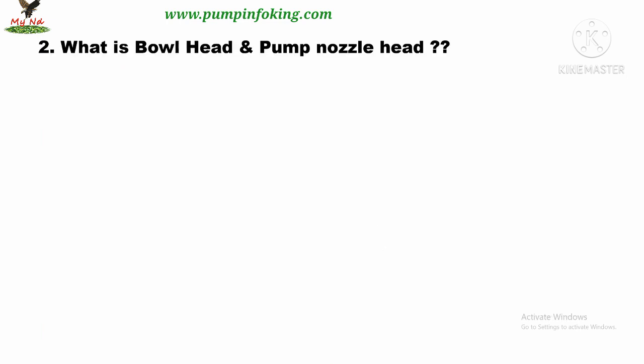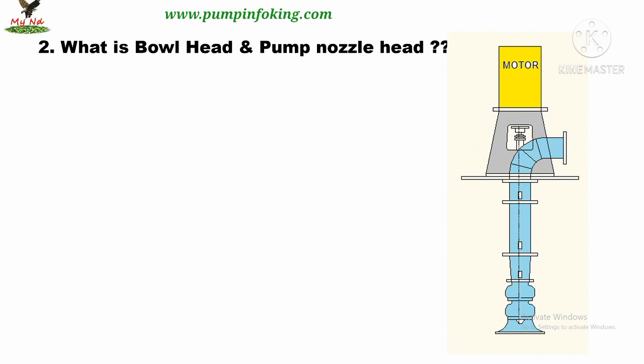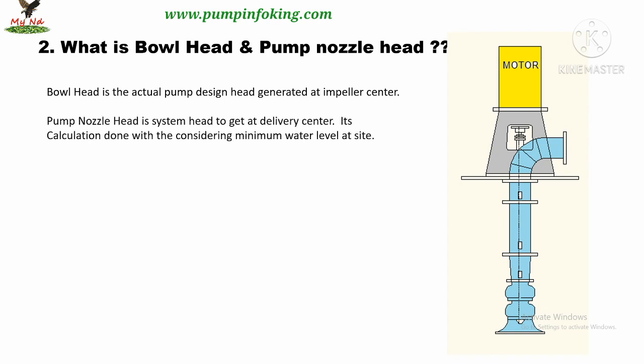So the next frequently asked question is, what is the bowl head and what is the nozzle head? Okay, so for this one, take the vertical turbine pump. Bowl head is the actual pump design head generated at the impeller center. Pump nozzle head is a system head obtained at the delivery center. It's a calculation done with consideration of the minimum water level at the site.